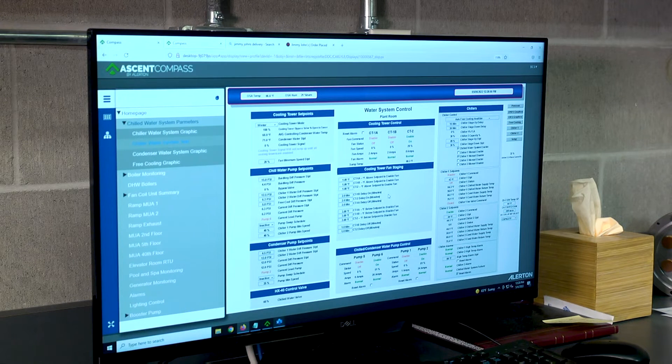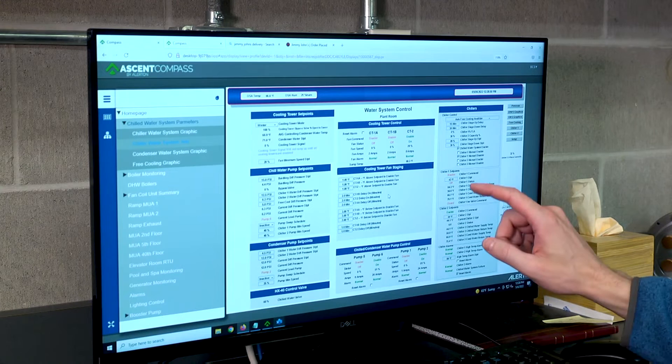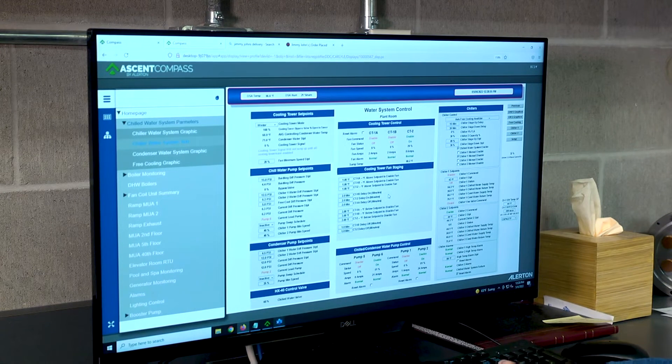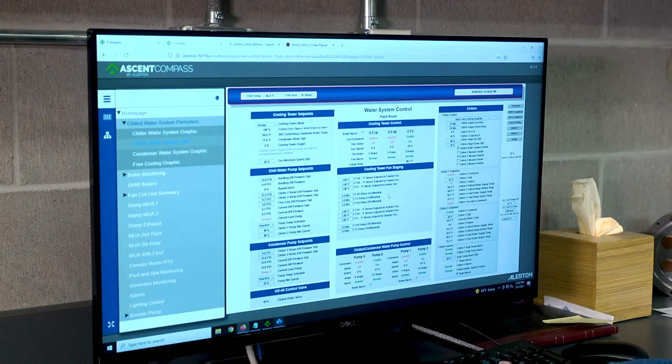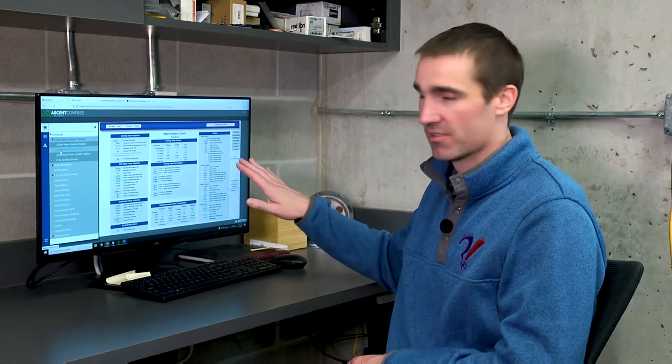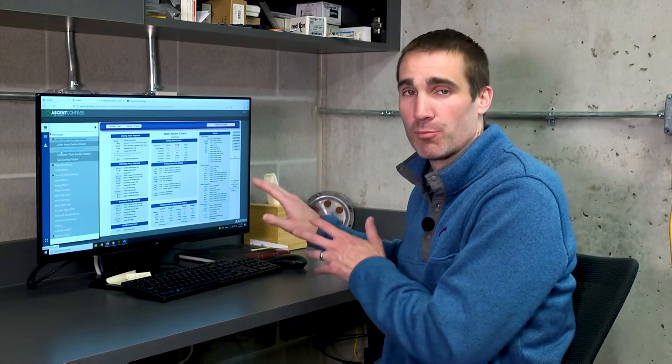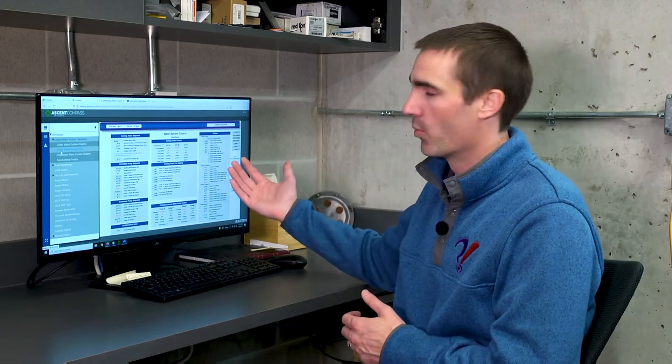In this particular case, we have chiller number one manually disabled. Even if the sequence of operations was calling for this particular chiller to be enabled, it would not be in this case because we have it overridden off. There is a reason for that that is appropriate right now for this particular system, but if it wasn't, it would be something we would want to release that override.